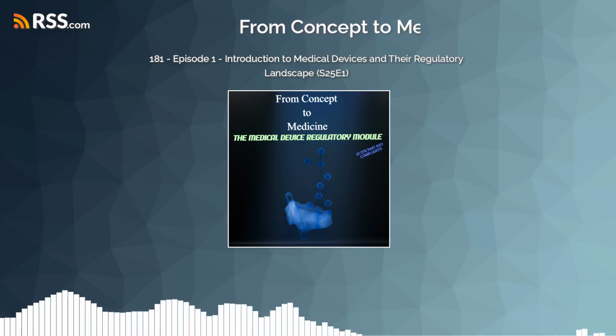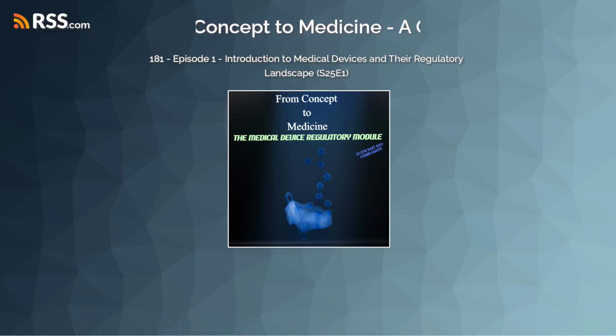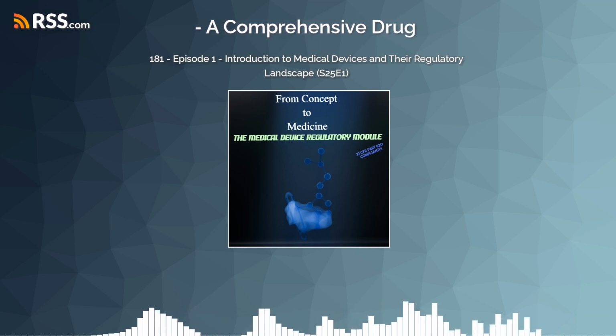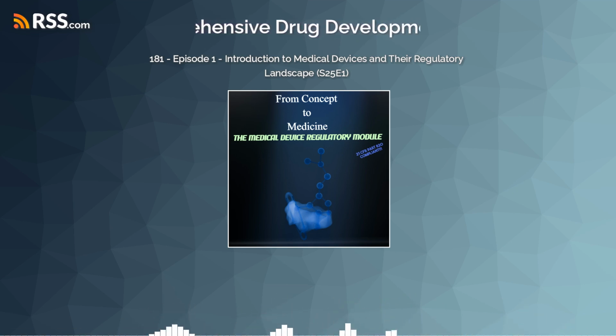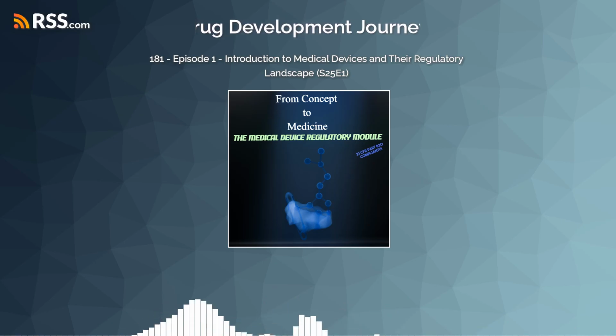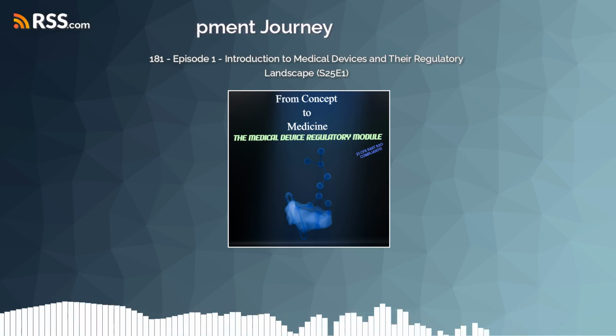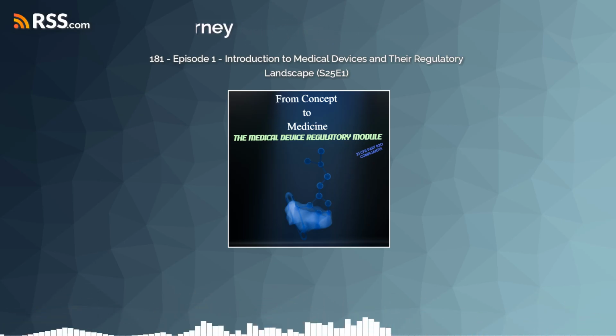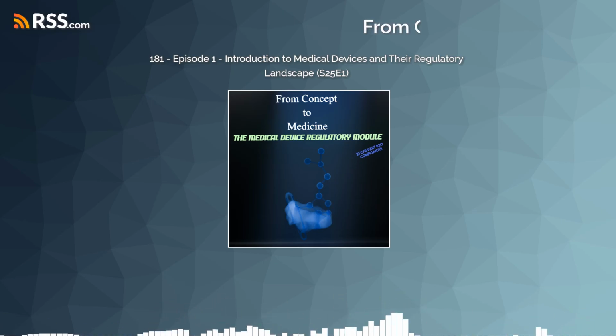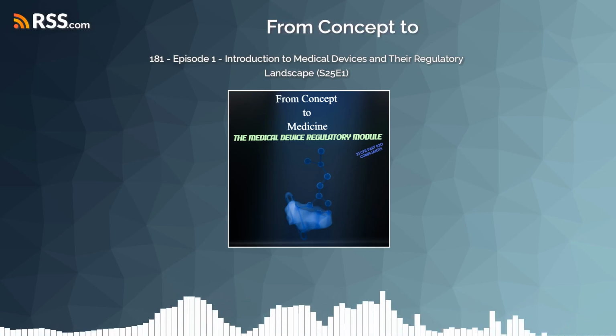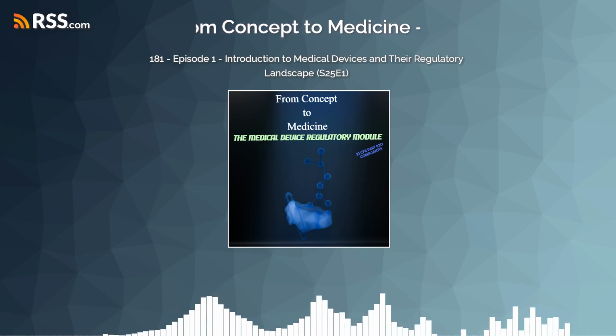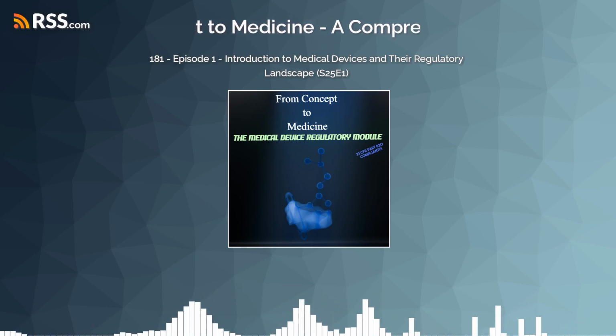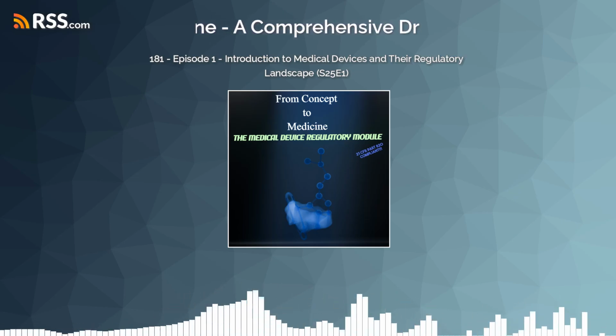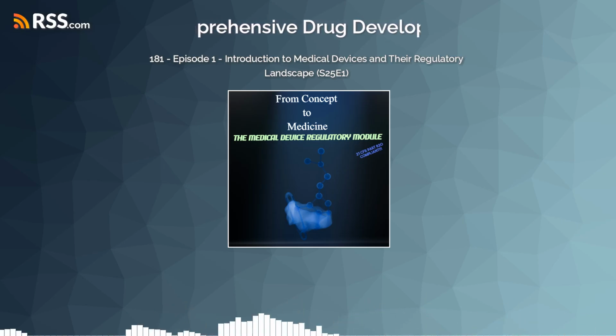Let's maybe start back at the beginning, how devices are designed and developed. Design controls are absolutely fundamental. The QMS guides the whole design and development process through structured documentation and rigorous risk controls. This includes having detailed design plans up front. And define what the device needs to do. Precisely. That's covered by design inputs. These are all the physical and performance requirements. They come from user needs, regulatory requirements, industry standards, everything that dictates what the device must achieve.